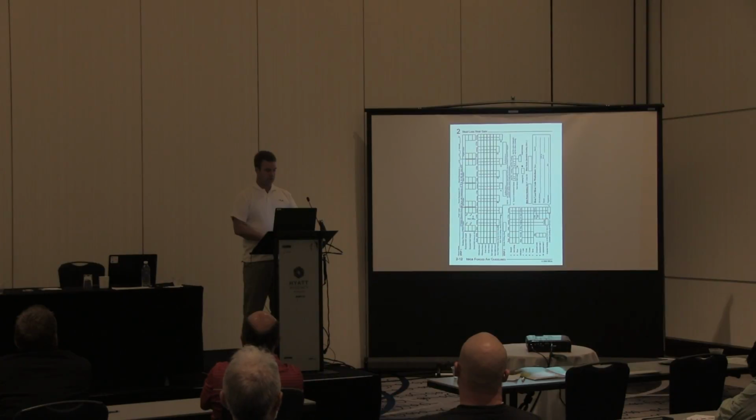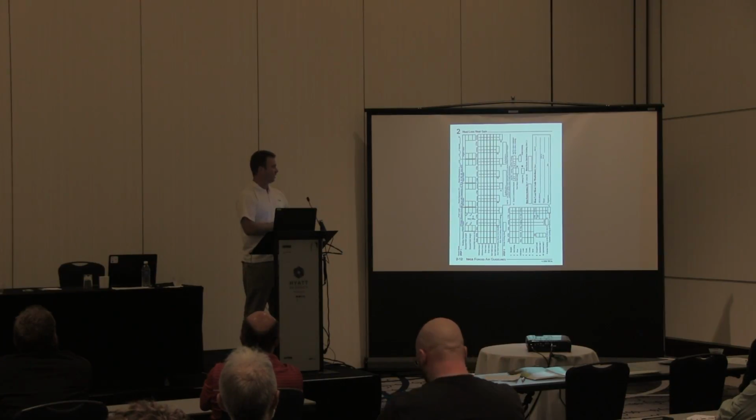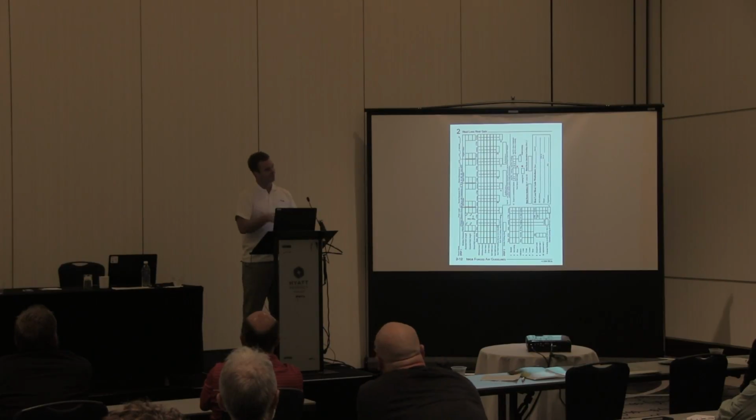Okay, so these are the sheets. I'm not going to go over the sheet. These are the sheets, if we did it longhand, that we teach the contractors how to fill out. So we do the north side, the west side, the east side, depending on how many exposed walls they have, and then we add up the square footage, add the windows and the doors and the ceiling and the floors and everything else, and do it longhand. Tekka does have a program that does this, so most guys take the class, learn how to do it, and then spend the $150 and buy the heat loss program and just enter the stuff in, and all the math is done for them, so they don't have to do it longhand anymore.